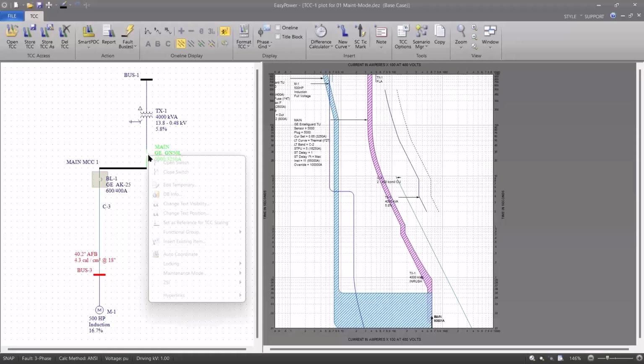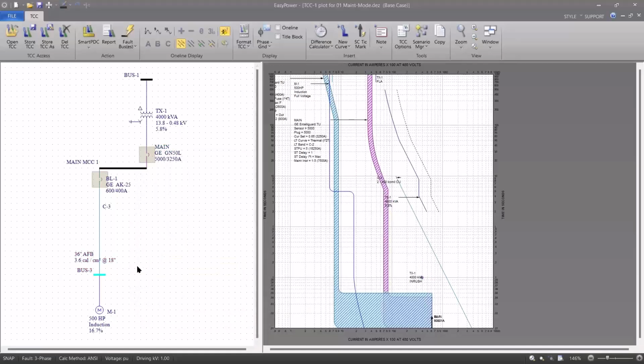If I turn on this breaker's maintenance mode, it brings down the 4 calories on both buses. So that infers that we need to have both of these on to get protection on this particular bus down below 4 calories. And likewise, this is a large motor.